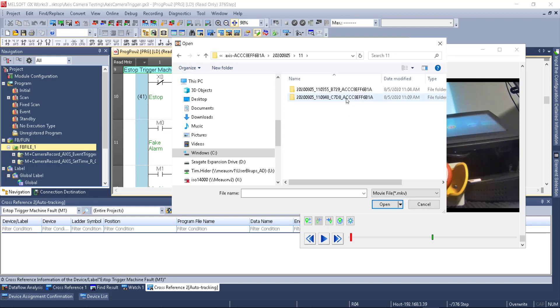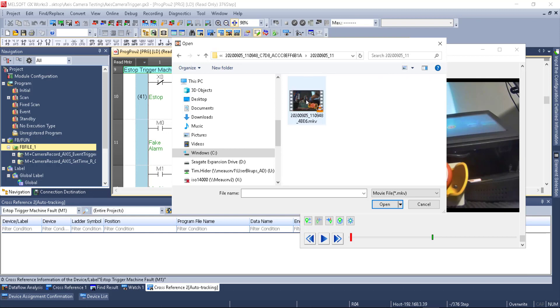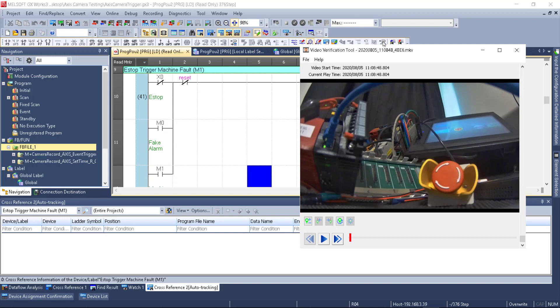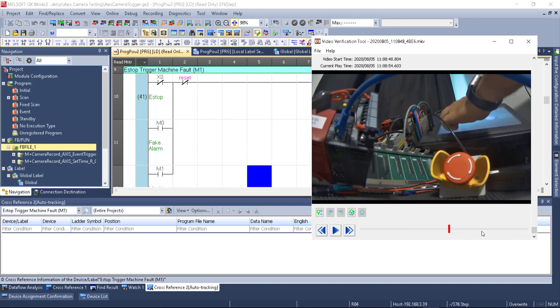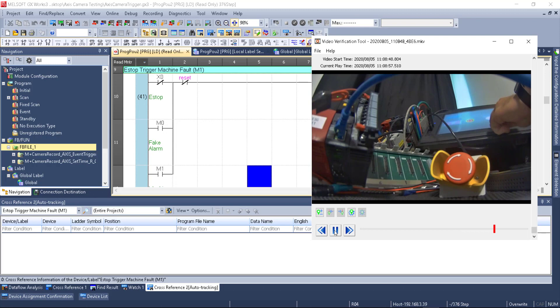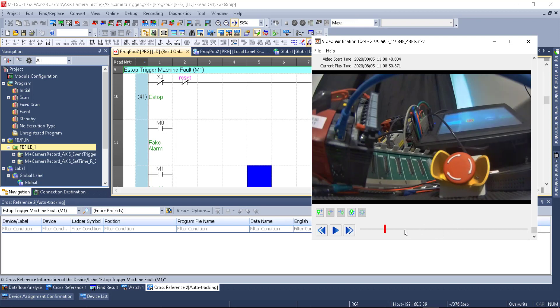We select 11 o'clock, choose the latest folder, double-click, and pull up the file. I can play the action and see that I triggered the screen — capturing about five seconds before and about five seconds after the event. The function block inside the PLC went out and captured this video file. Within here we could also put logging markers as points of interest and flip back and forth between them to watch the video update. Adding a log marker file adds information to the folder and will remember those markers from here on out.